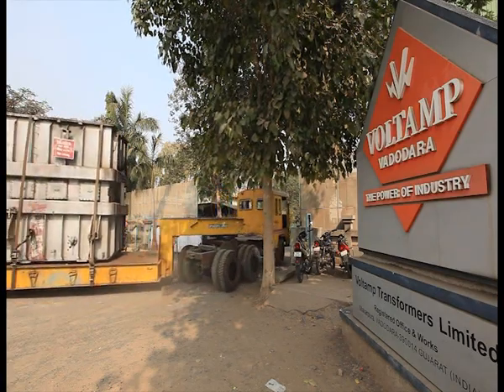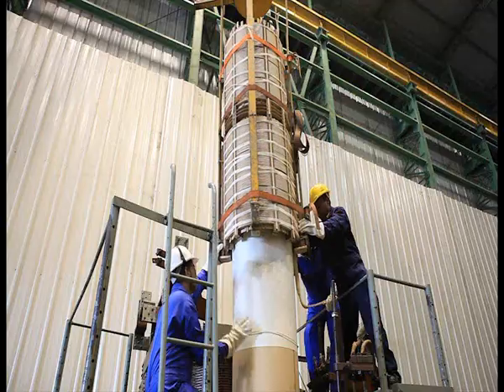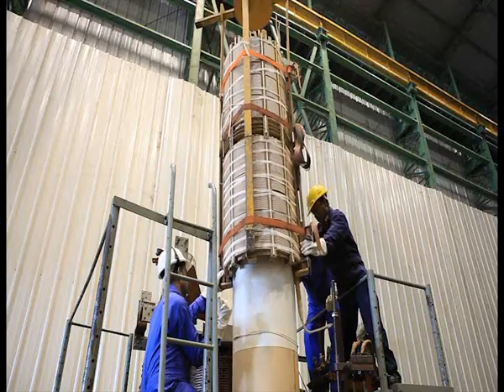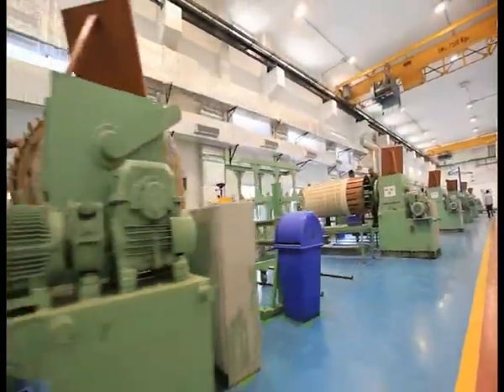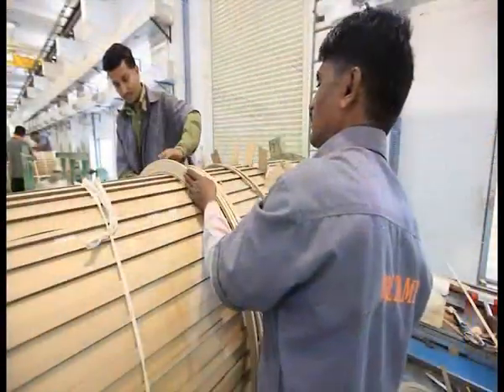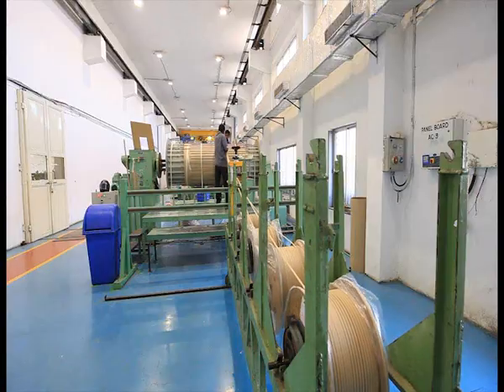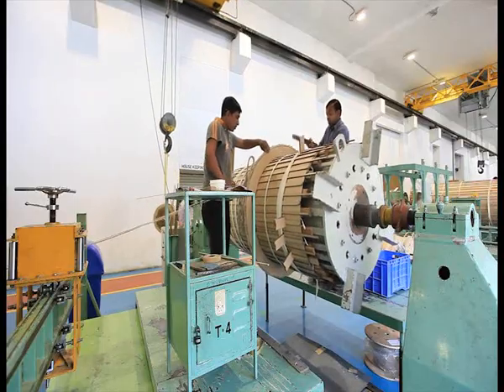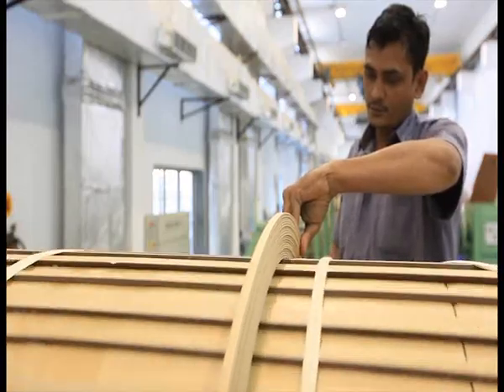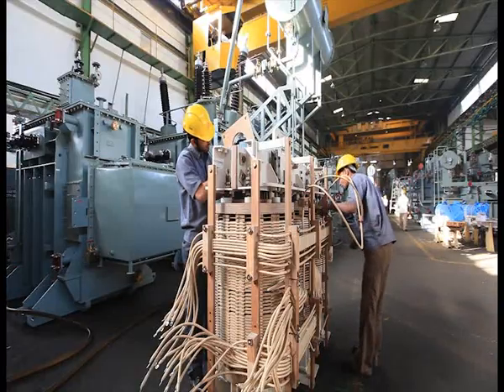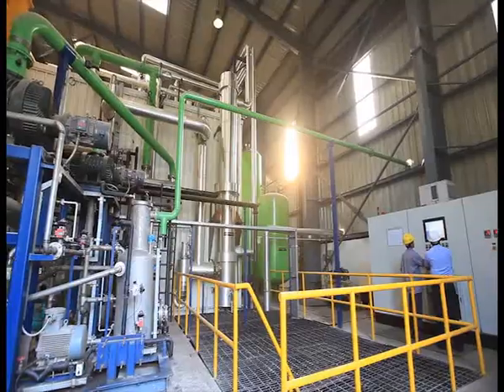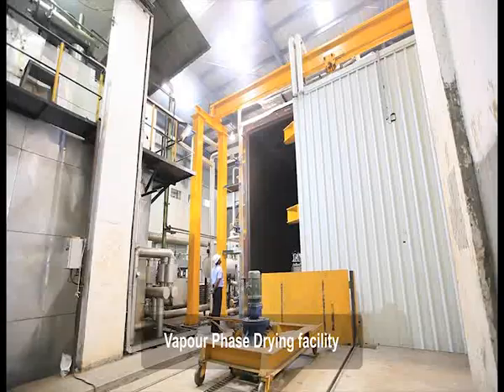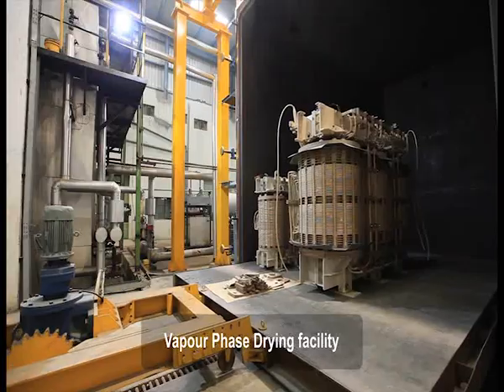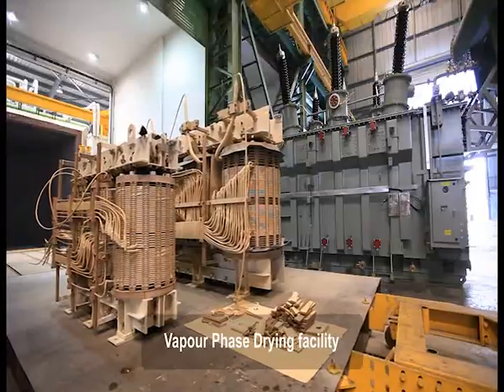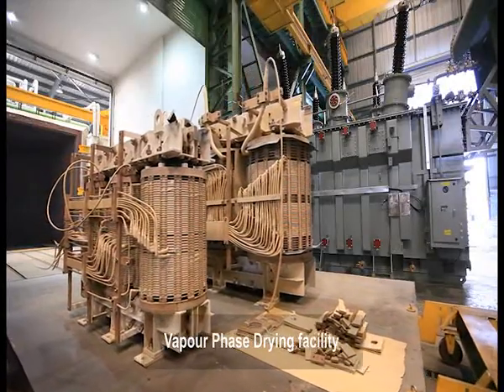In case of major repairs like winding replacements, the transformer has to be brought to our Vadodara works for repairs. In such cases, new winding preparation takes place in our dust and moist-free winding shop. Experienced winders work at micro-level accuracy and checks. Core coil assemblies of repaired transformers undergo vapor phase drying, the latest and most advanced technology to eliminate moisture from core and winding assemblies.